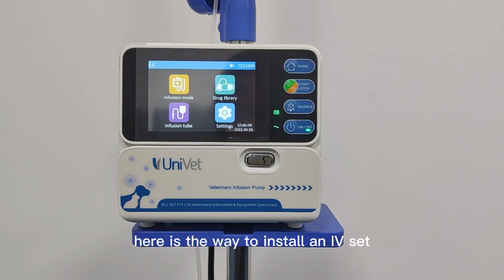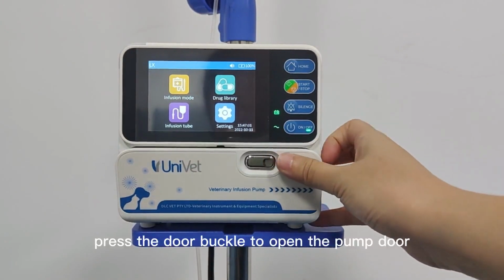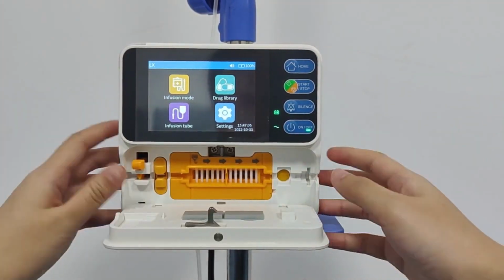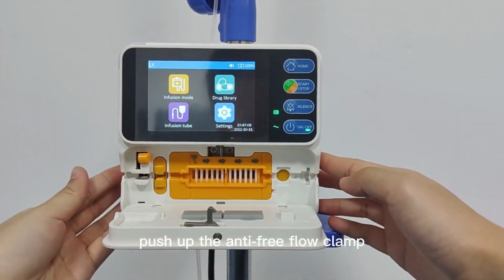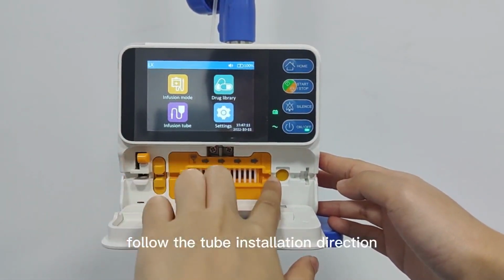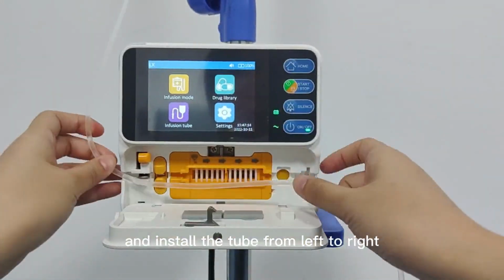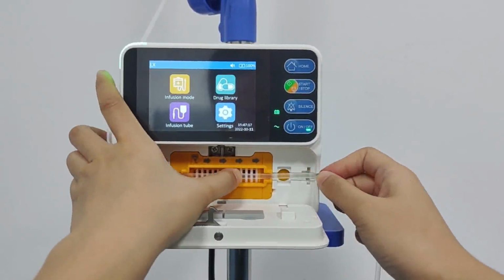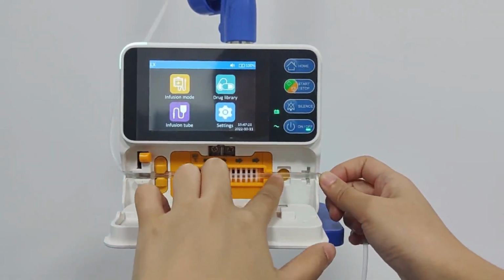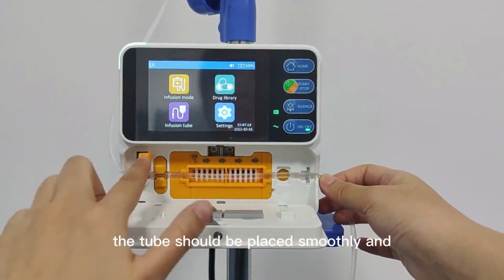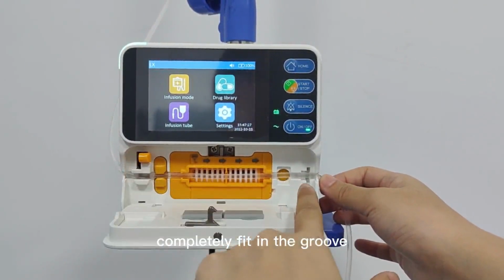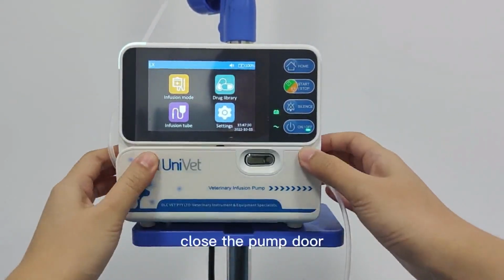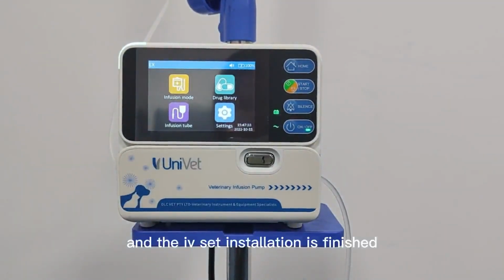IV set installation. Here is the way to install an IV set. Press the door buckle to open the pump door. Push up the anti-free flow clamp. Follow the tube installation direction and install the tube from left to right. The tube should be placed smoothly and completely fit in the groove. Close the pump door and the IV set installation is finished.